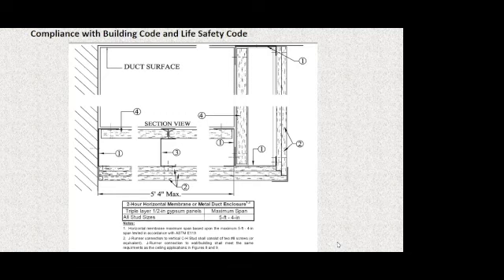going to be down on the floor once it actually gets hot, because at 70 degrees, it may well stay up there. But ambient is not what we're aiming for. We're aiming for it to stay up there and protect that duct at 2000 degrees for 2 hours. And if it's not this design, then it doesn't exist for drywall.